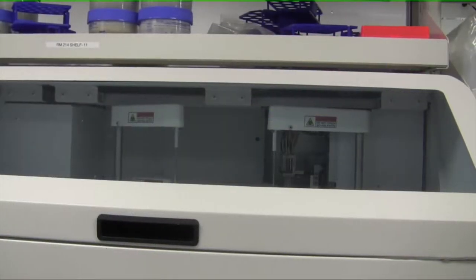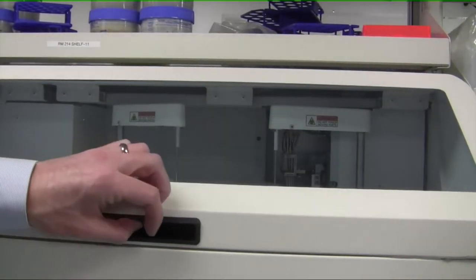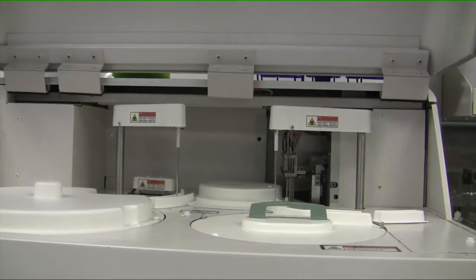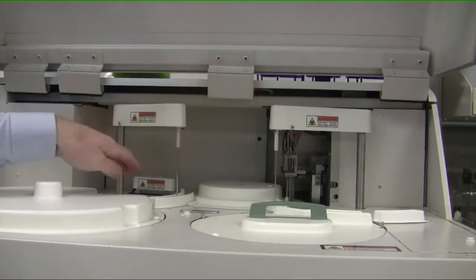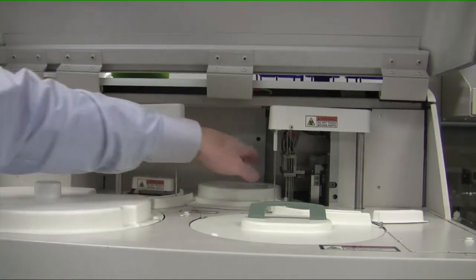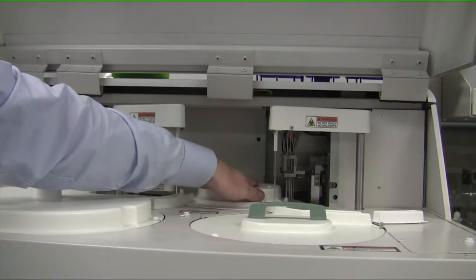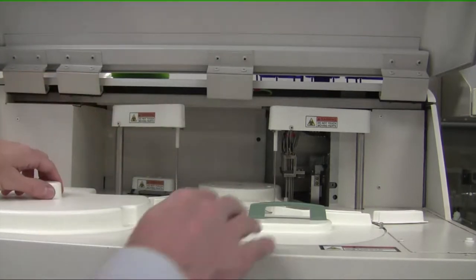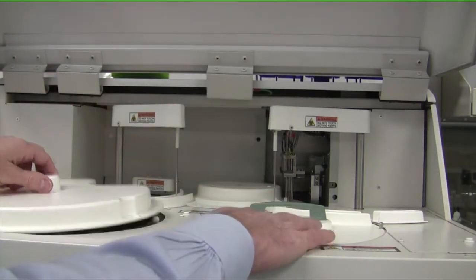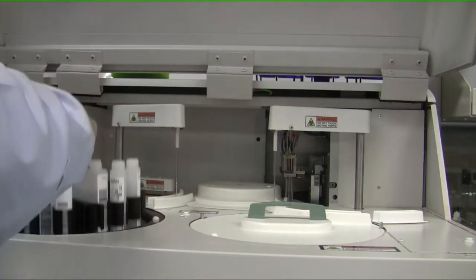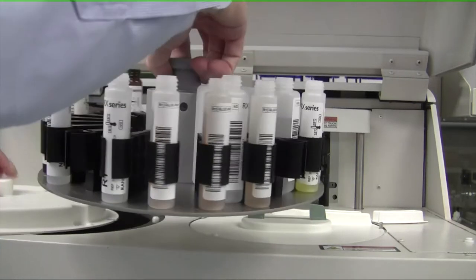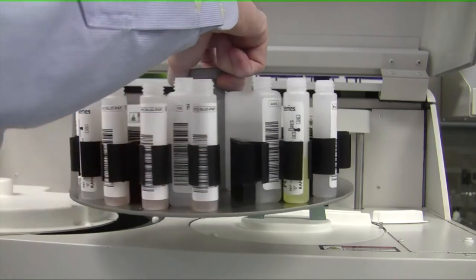I can now give you a brief overview of the hardware. If we open up the lid of the instrument, you're going to see that there's two pipetting arms, one mixer. Underneath here is where all the cuvettes are stored. And then we have two chambers here. One is for the reagents. So each bottle itself would be for a specific reagent.